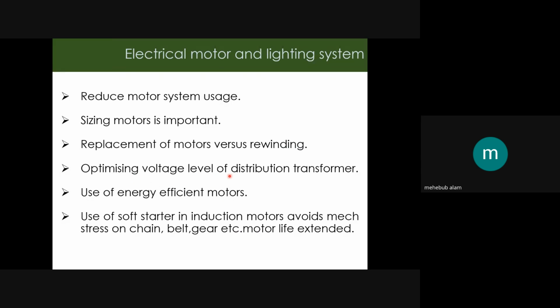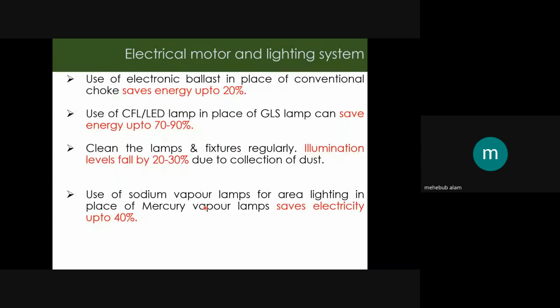Optimizing the voltage level of the distribution transformer used in the thermal power plant, and use of a soft starter in the case of an induction motor, because it avoids mechanical stress on the different drives like chain, belt, gear, and conveyor, and it will also extend the motor life.